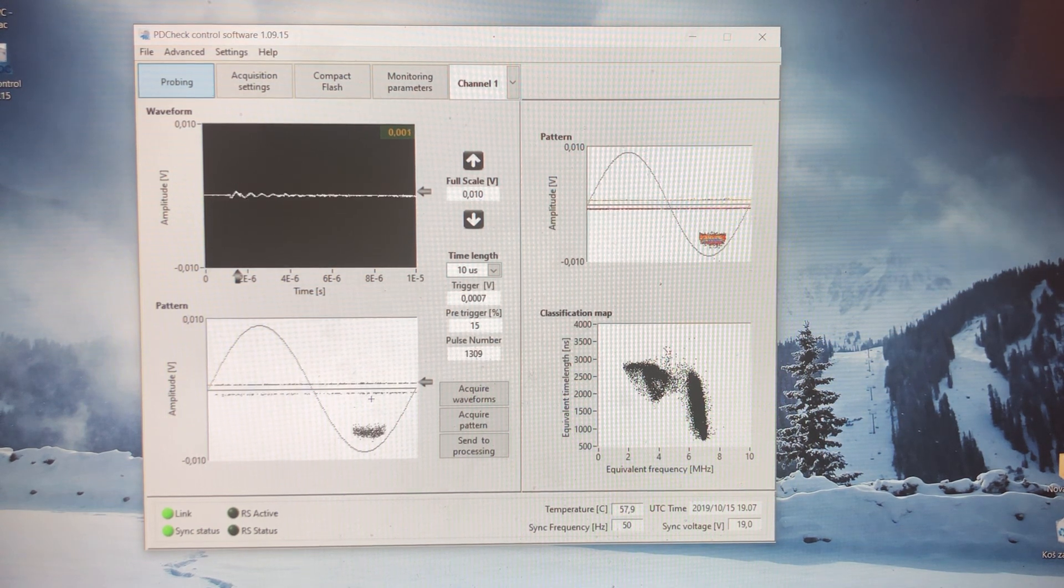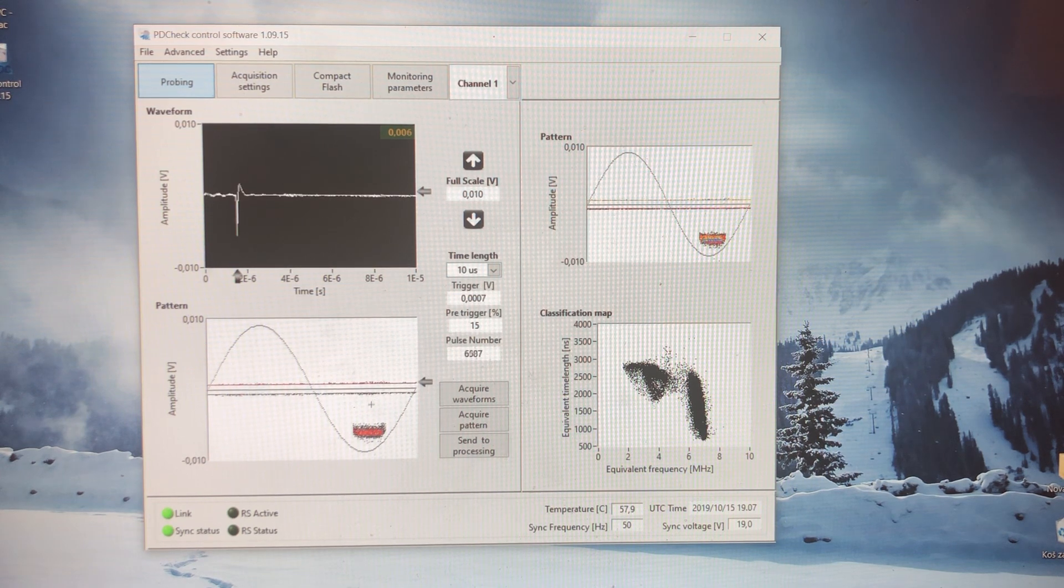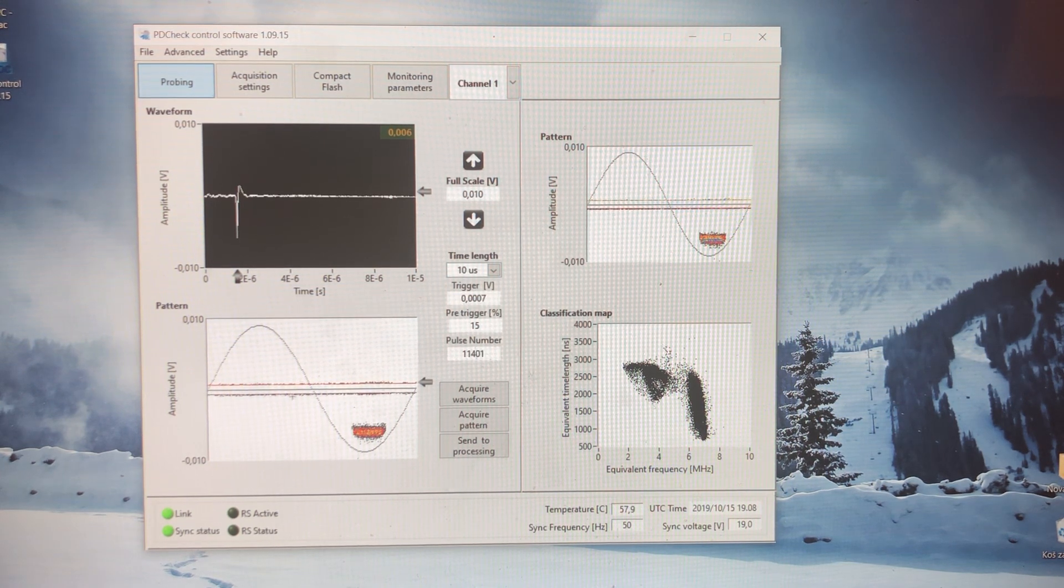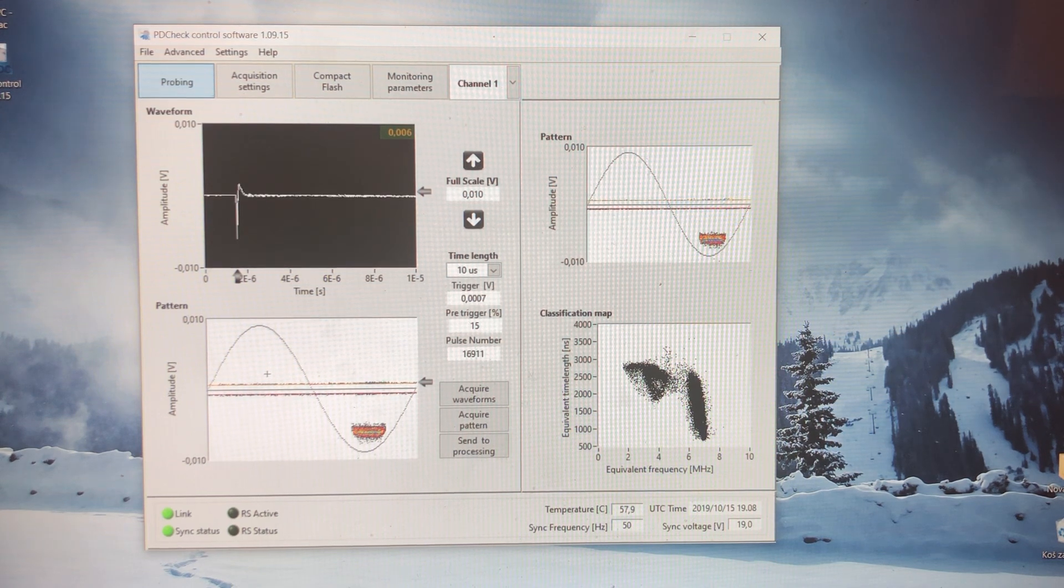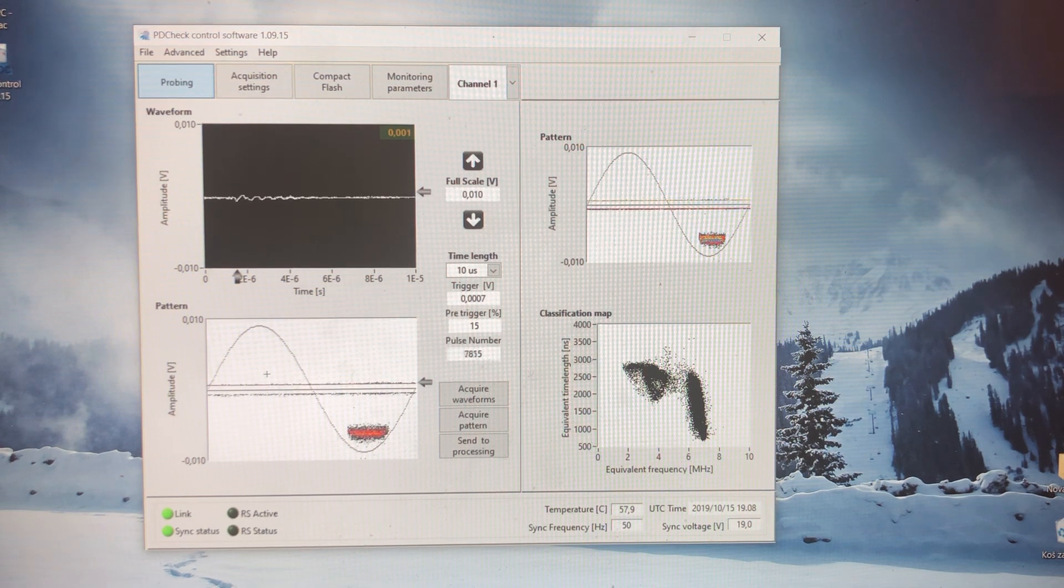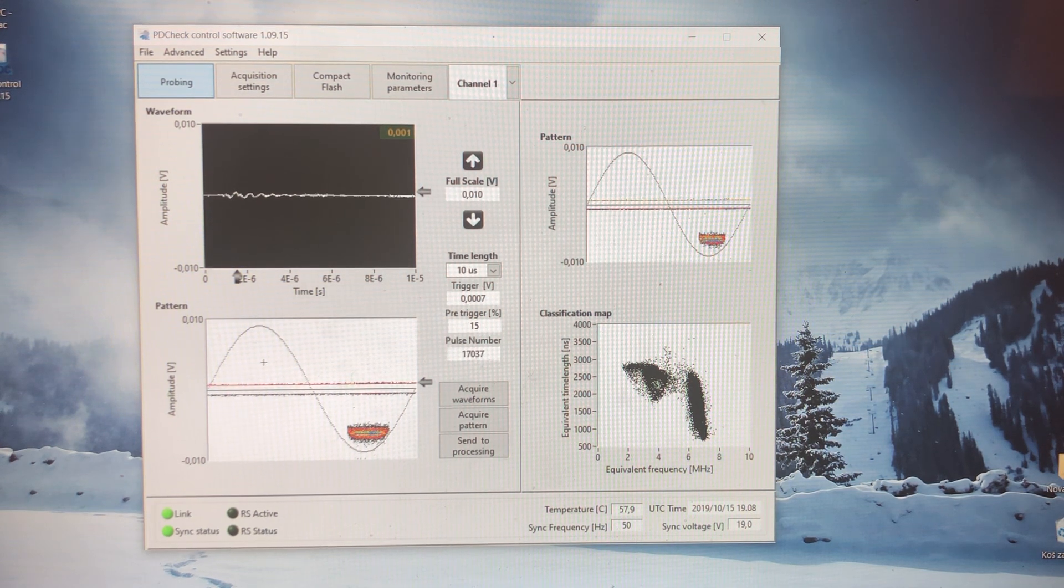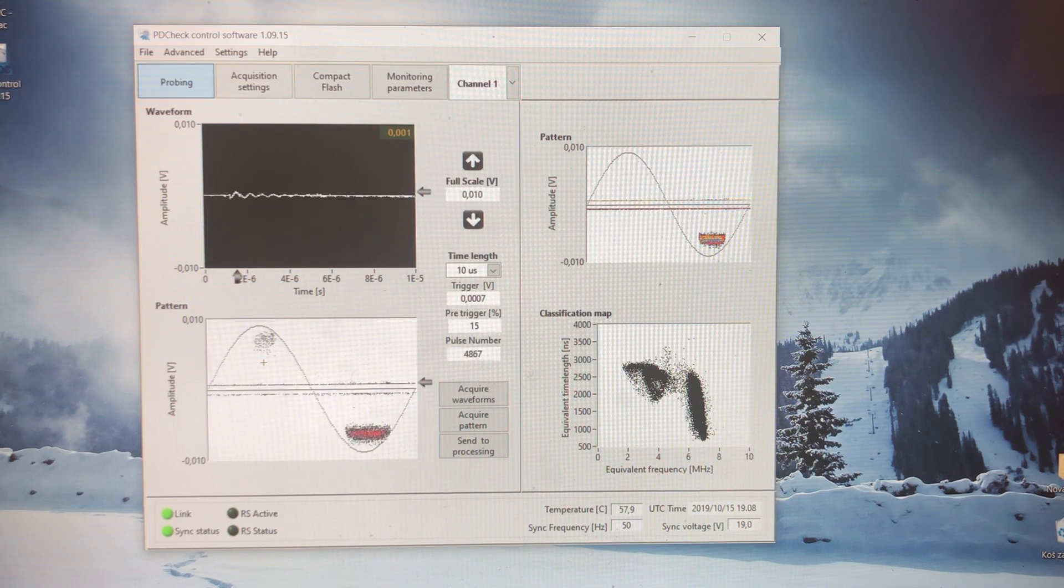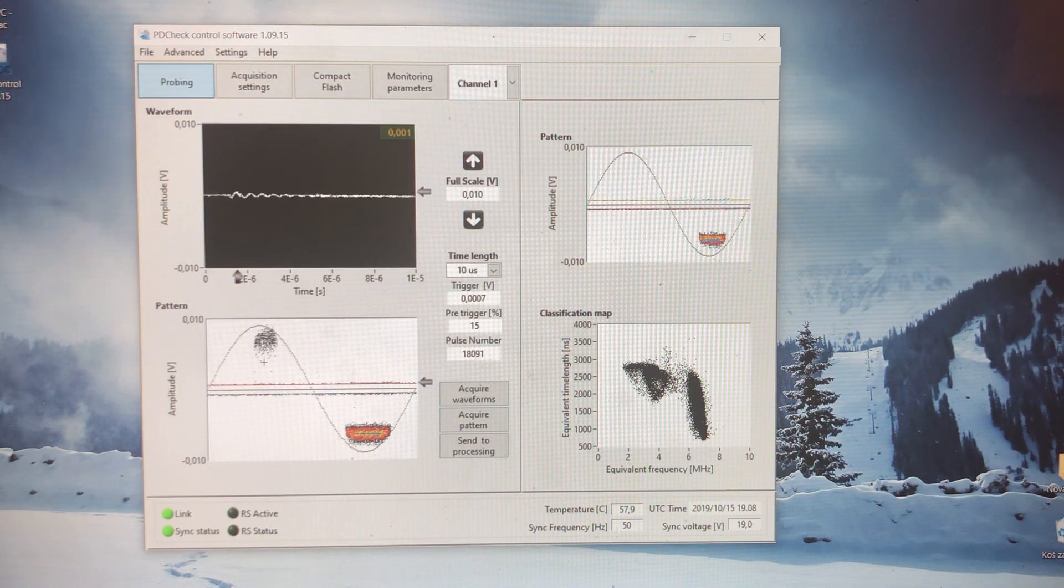I will now increase the voltage, and we will see one more thing. Right now we see the corona just in the negative half cycle. As I increase the voltage, which you can see right now, slowly but surely you are going to see some dots happening here. And we see that just about now.